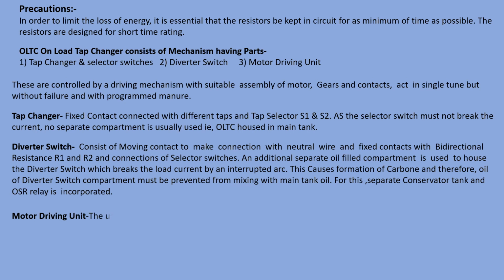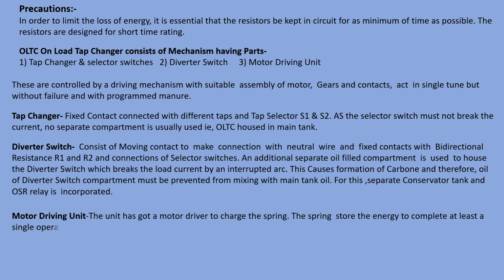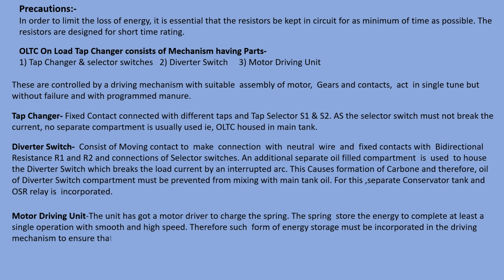Motor driving unit. The unit has a motor drive to charge the spring. The spring stores the energy to complete at least a single operation smoothly and at high speed. Therefore, such a form of energy storage must be incorporated in the driving mechanism to ensure that a tap change, once initiated, shall be completed even in case of failure of auxiliary power supply.